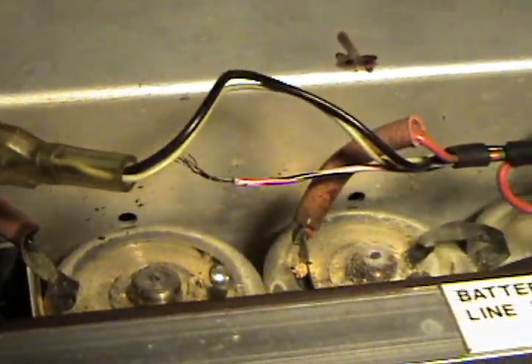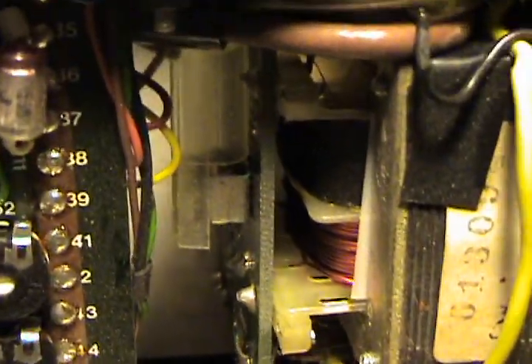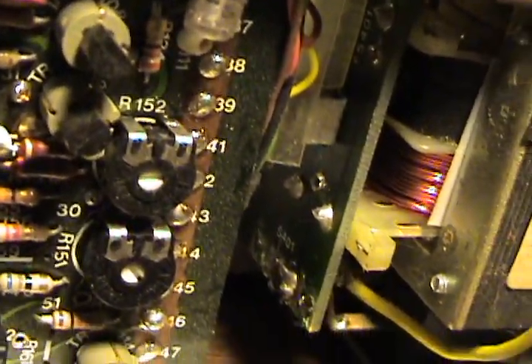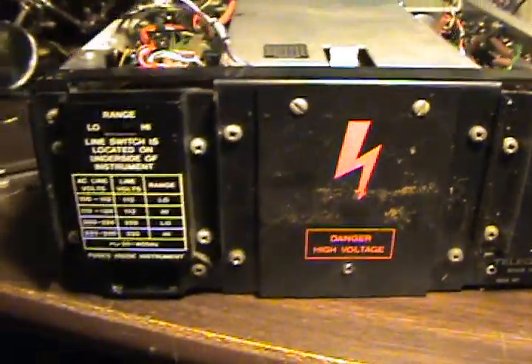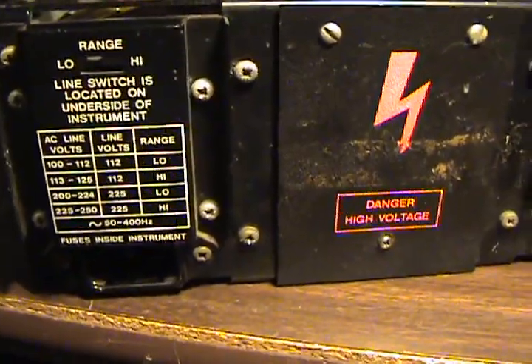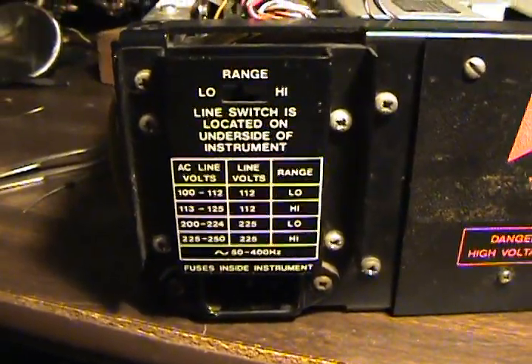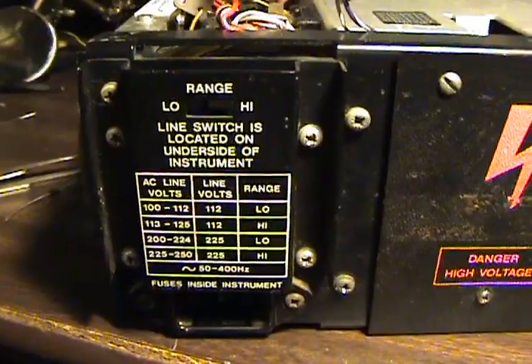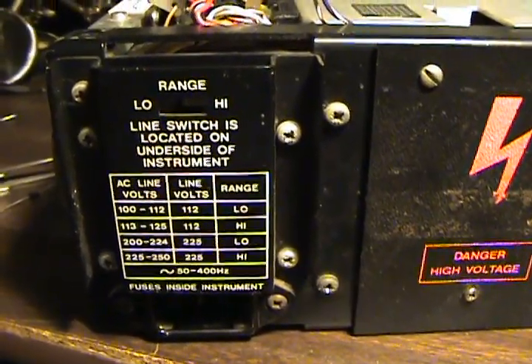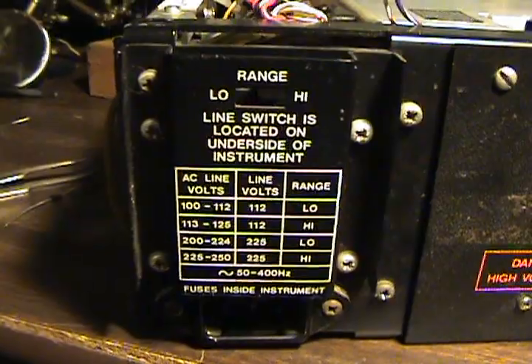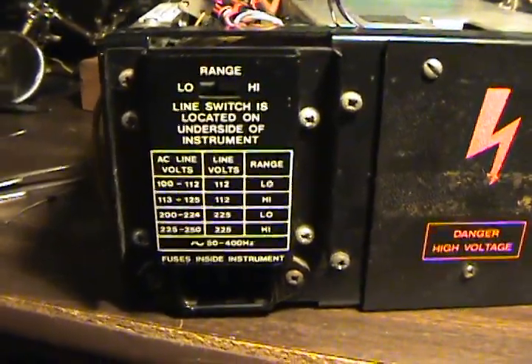So maybe they've been replaced before, but they need replacing again. I've had all of this apart to get in at this. You can kind of see it there, power supply board soldered direct to that transformer because the battery leaked into it and ruined the line voltage switch, line switch located on the underside of instrument. Well, it's not anymore because that switch was destroyed by the battery leakage.